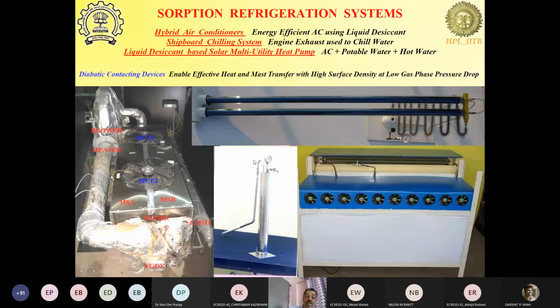And this adsorption technology can be as simple as this, where you have an activated carbon, or adsorbent, module with an appropriate heat transfer enhancing mechanism inside the module. When you heat this module, the pressure goes up because of desorption, and the pressurized refrigerant condenses on the other side if it is kept at ambient. After most of the ammonia has been driven out of the adsorption system, we stop heating and bring it back down to ambient using either air cooling or water cooling. Then the pressure goes down, and at low pressure your ammonia evaporates, and as you can see, there is frosting on this particular part here. So without moving any valves, just by switching the heating and cooling circuits on and off, you can produce cooling.